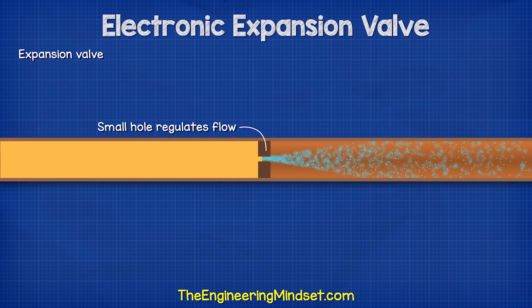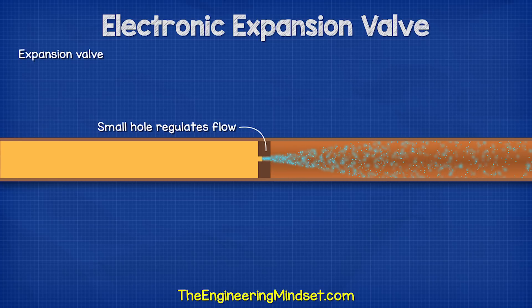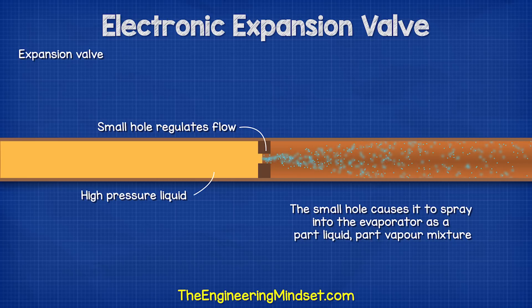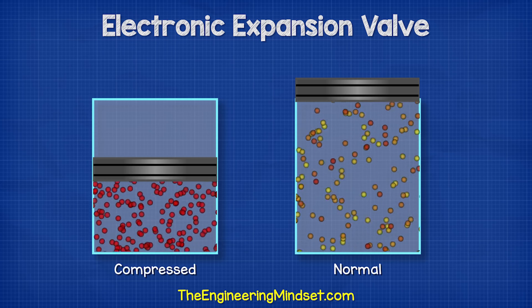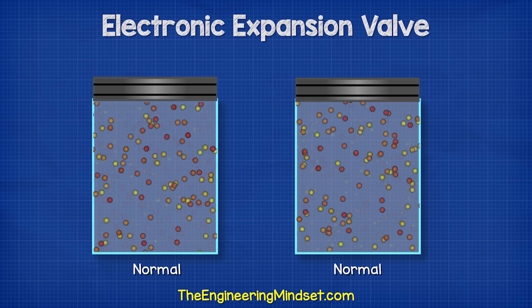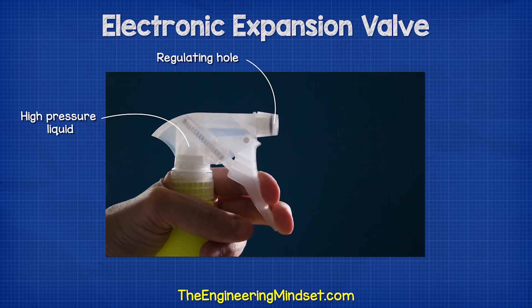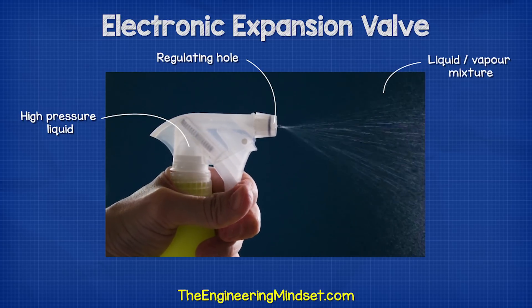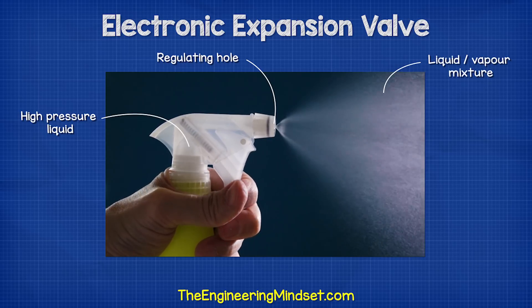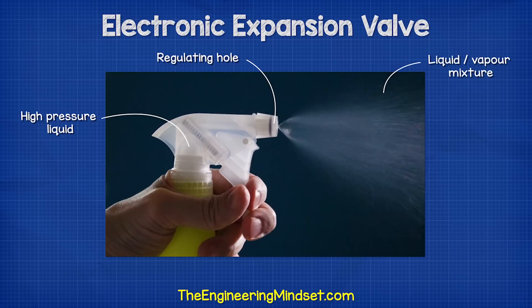The expansion valve regulates the refrigerant by only allowing it to pass through a small hole. This creates a large pressure difference across the valve — one side is the high pressure liquid, the other side is almost empty. The small hole causes it to almost spray into the evaporator as a part liquid, part vapor mixture. The refrigerant will expand to try and fill the empty space on the other side and this will cause it to drop in pressure as well as temperature. It's a little bit like spraying a deodorant can — it flows through a small hole causing it to expand as a part vapor and part liquid mixture, and then we can feel the can become cooler.